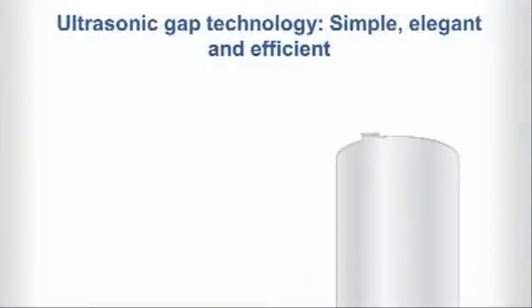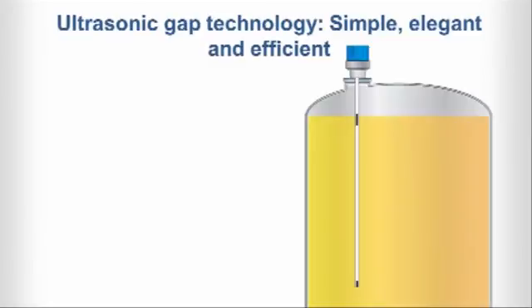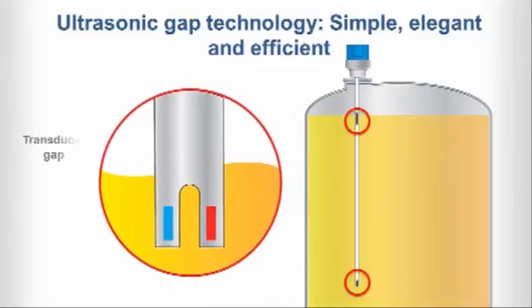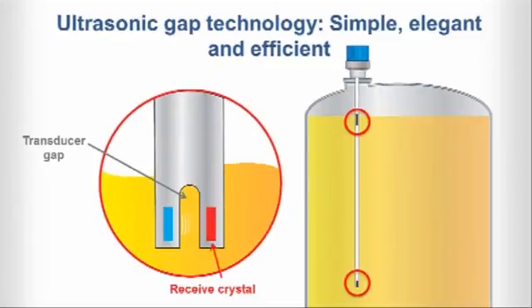The pulse signal technology utilized by our Echotel Models 961 and 962 switches can easily handle your most challenging process conditions. Pulsed sound waves are transmitted across a transducer gap when liquid media is present, but are attenuated when the gap is dry. That's why the density of the liquid media doesn't matter. When liquid is present in the gap, a receive crystal senses the ultrasonic signal from the transmit crystal and converts it back to an electrical signal. The signal is then sent to the electronics to indicate the presence of liquid in the transducer gap. This simple, elegant, efficient process is also called ultrasonic gap technology.